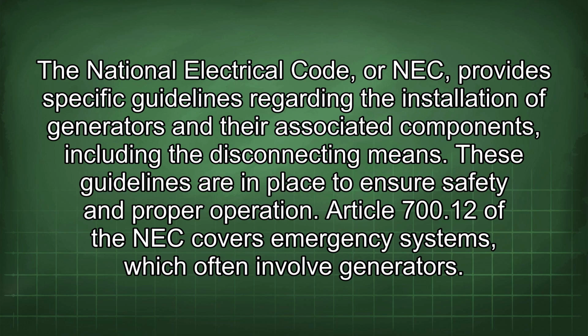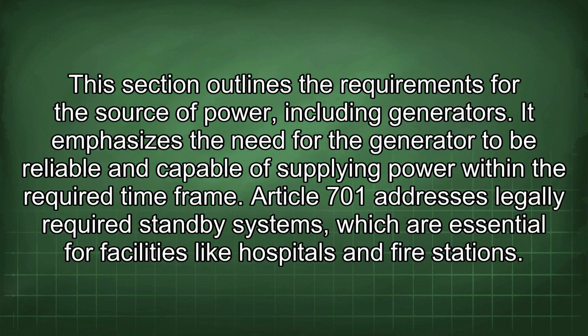The National Electrical Code, or NEC, provides specific guidelines regarding the installation of generators and their associated components, including the disconnecting means. These guidelines are in place to ensure safety and proper operation. Article 700.12 of the NEC covers emergency systems, which often involve generators. This section outlines the requirements for the source of power, including generators. It emphasizes the need for the generator to be reliable and capable of supplying power within the required time frame.